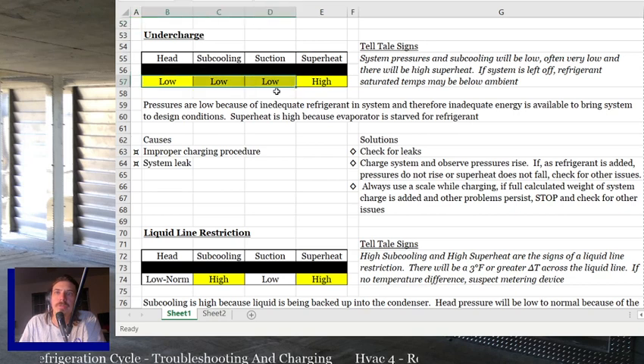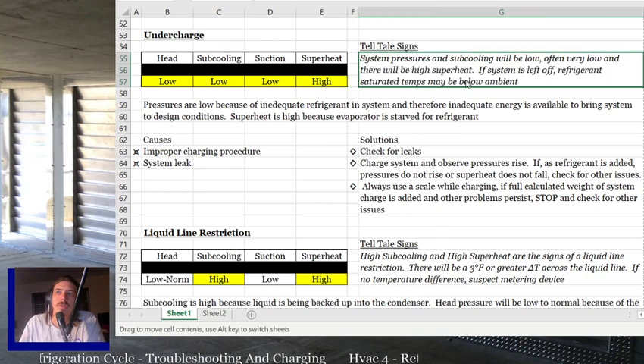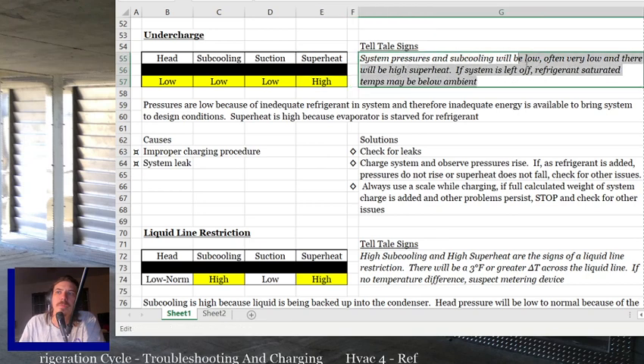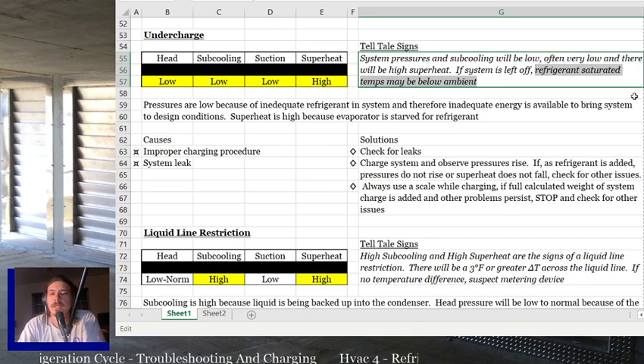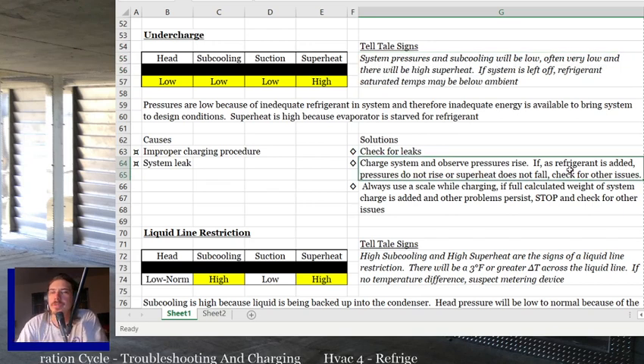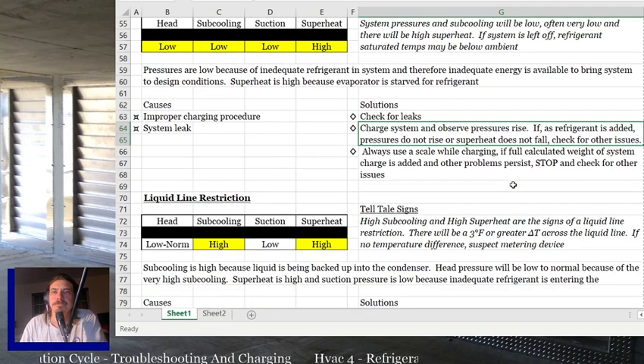Make sure everything else looks low and you've got high superheat. Odds are you're undercharged, and then look for that refrigerant saturated temp to be below ambient. That is really your telltale sign of a real undercharge. A lot of times by the time you get to an undercharge, it's 2, 3, 4 pounds low, something like that anyway, because it'll usually work just enough that they don't call you till it's a good few pounds empty, and you'll see the undercharge pretty quick if that's what it is. Any questions on an undercharge?